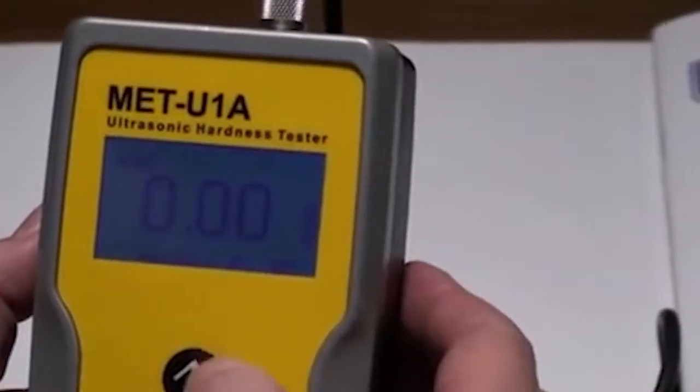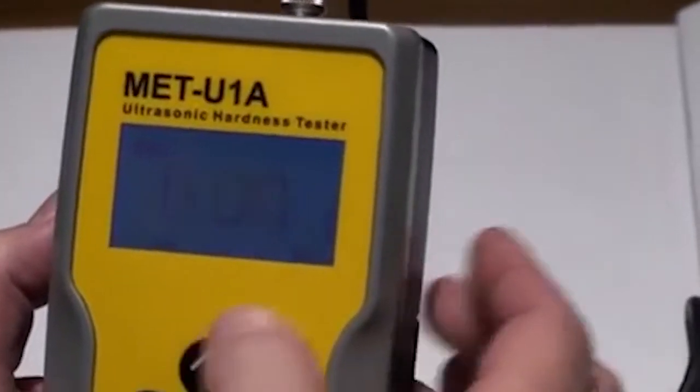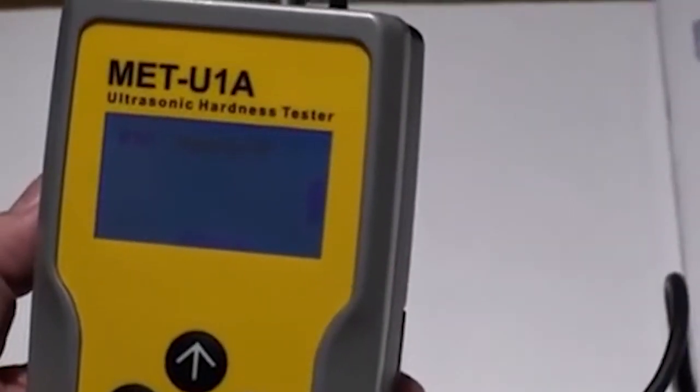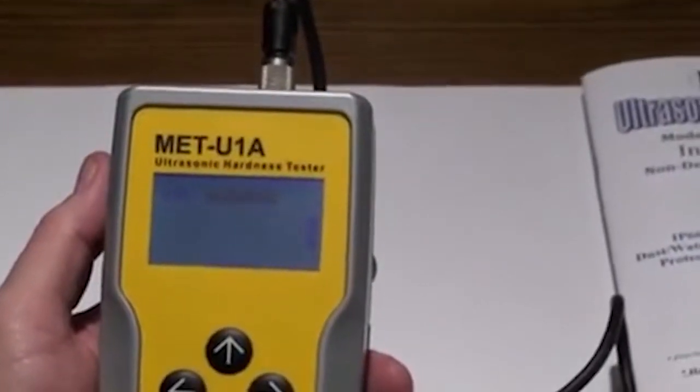Hitting the up arrow button, you now see the word test flashing with arrows left and right. Hit the up arrow again, and this will bring us to the scale. You will now see the word scale flashing with arrows. Left of this is the scale now being used, probably HRC, used for steels.